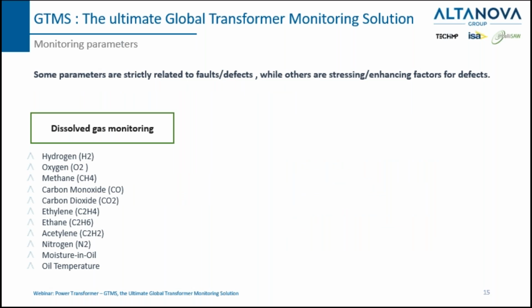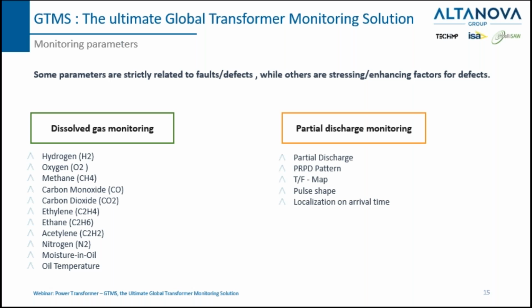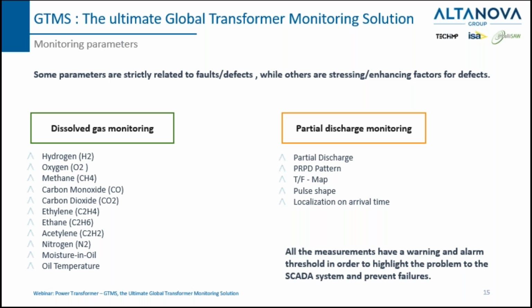And you can see here the other 2 modules. One is dedicated to the DGA analysis. We can have from 1 gas up to 9 and more gases according to the client specification and requirements. And the last module is for partial discharge monitoring, in order to detect, identify, and analyze the partial discharge activity and trends inside the transformers. For all these measurements and parameters, we have warning and alarm thresholds that we can set in the system in order to highlight problems and communicate them, in other words alarms, to the SCADA system, in order to prevent failures.